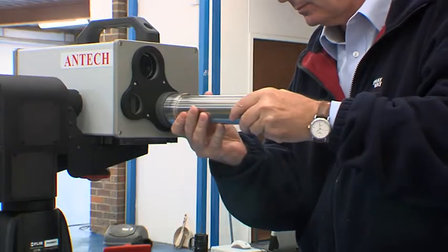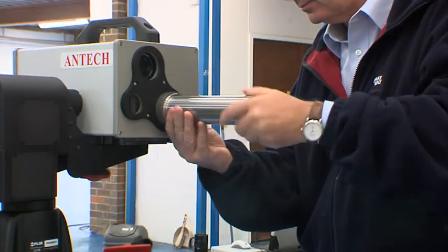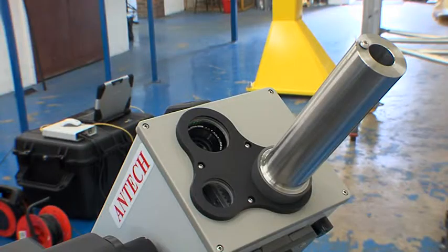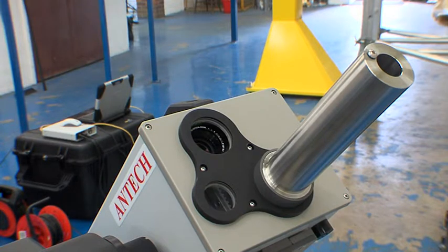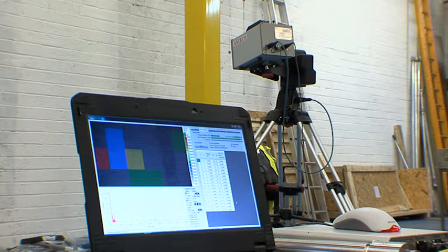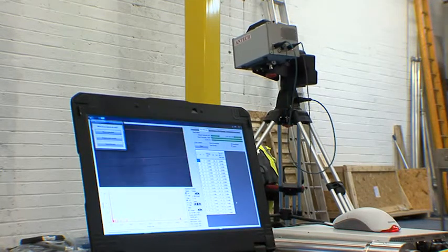With the detachable collimator fitted, the RadSearch detector has a field of view of 4 degrees, and this determines the size of the scan element. With the collimator barrel removed, RadSearch can be used to scan large areas with a detector field of view of 18 degrees.